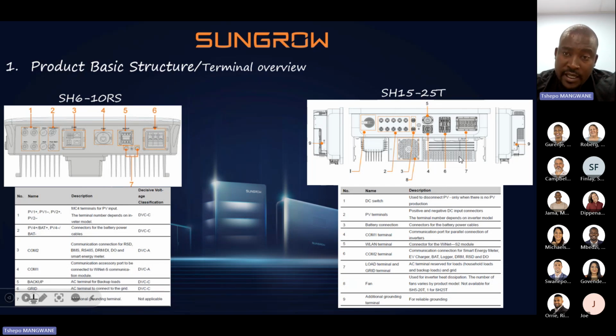Regardless, why am I saying it's a split phase inverter? Should phase 2 and phase 3 be missing, phase 1 will continue producing without phase 2, phase 3 demand on them. Okay. So though it will work separately, it works mostly like a single phase. Wherever there's power needed on each phase, it will provide accordingly to that phase.